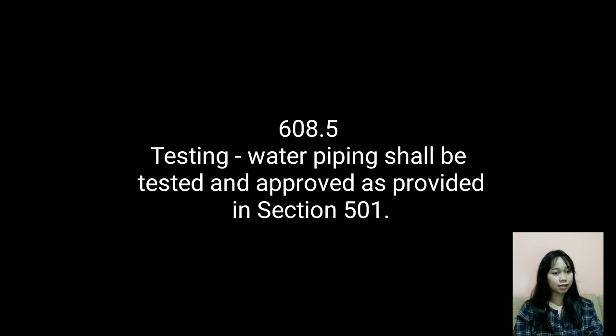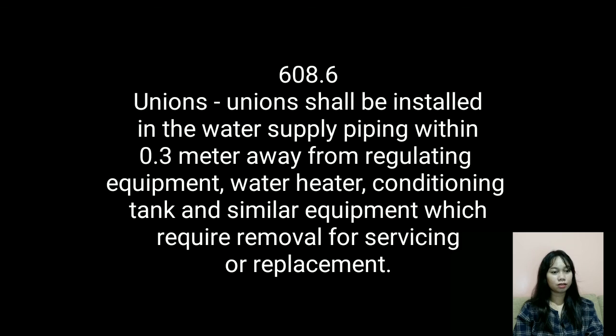Section 608.5: Water piping shall be tested and approved as provided in Section 501. Section 608.6 — Unions: Unions shall be installed in water supply piping within 0.3 meter of regulating equipment, water heaters, conditioning tanks, and similar equipment which requires removal for servicing or replacement.